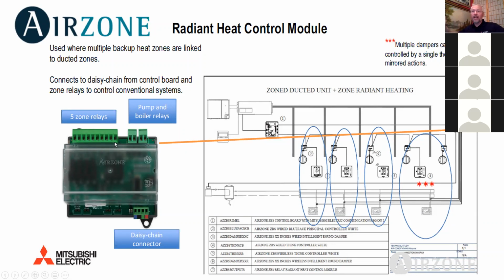So if you had an AirZone system that had 10 ductless systems, or some number of ductless systems and some radiant or whatever else, but then on top of that you had backup zones for any one of those particular zones, you would wire them to the corresponding ports on this relay module. And then within the control structure, you can say, hey, use the heat pump, and here's my secondary. You turn on radiant heat zone, whatever, 3. And it's able to do all of that. Now, it is possible through a third party to buy a Wi-Fi card that plugs into this to enable you to do it all online.